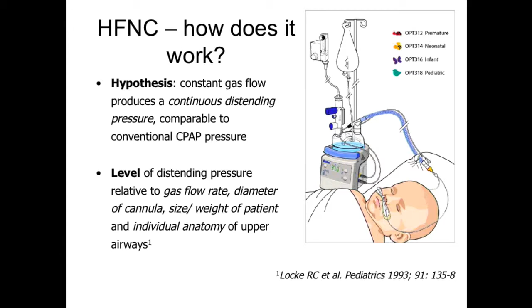And the level of this distending pressure, the CPAP pressure that it produces, depends on the size of the baby, the flow of the gases, the cannula size and everything. So you do not actually know what you do. But usually in the studies that have been done, you can measure pressures up to 4 to 5 centimeters, with flows up to 6 or 7 liters, but it's very variable.